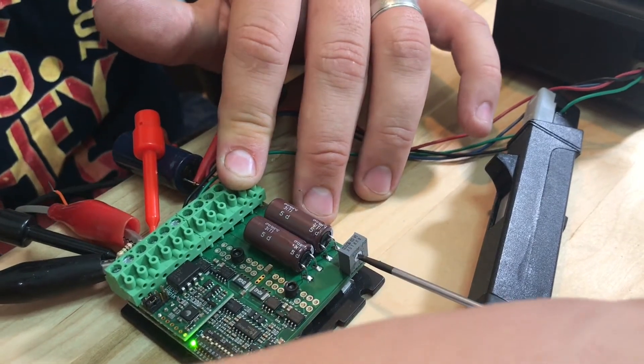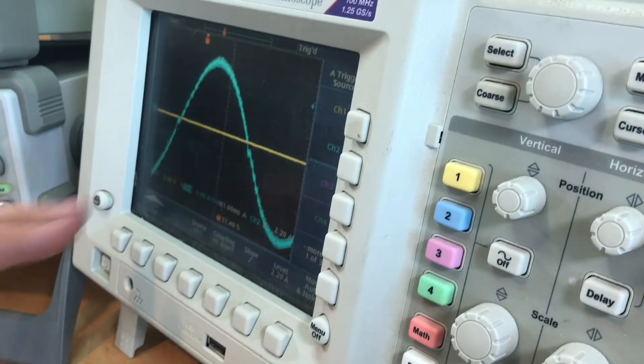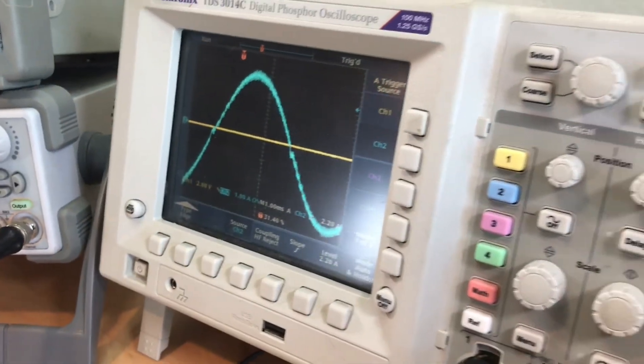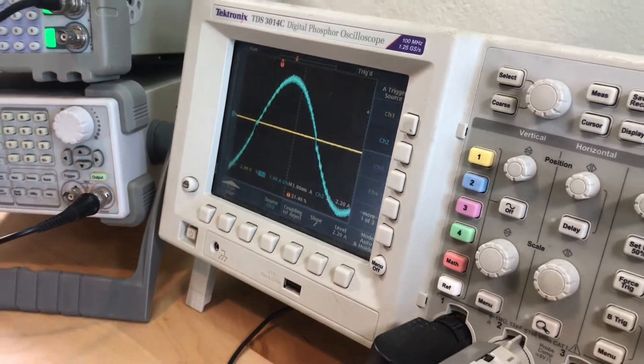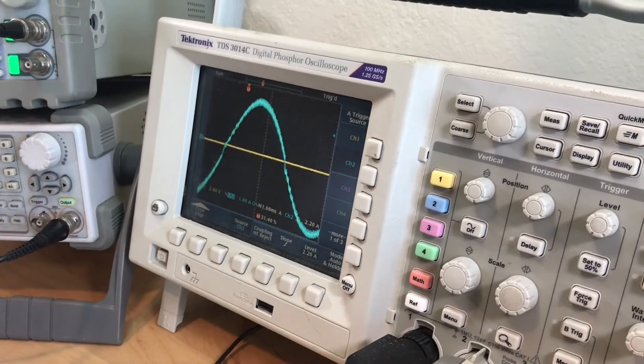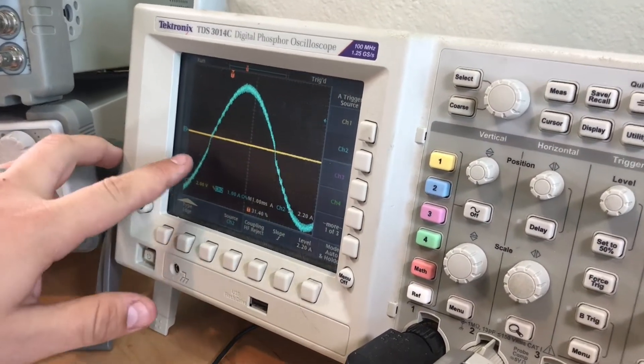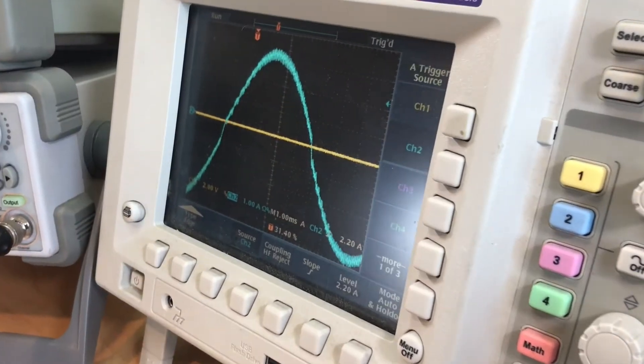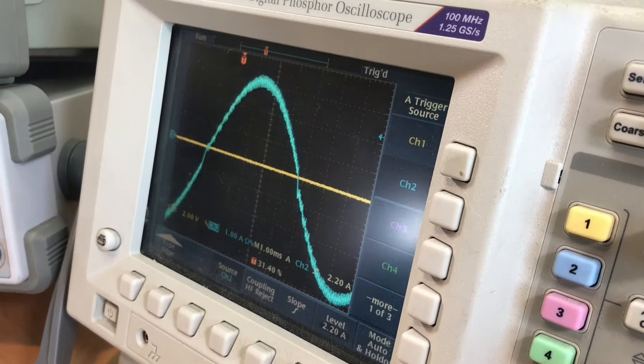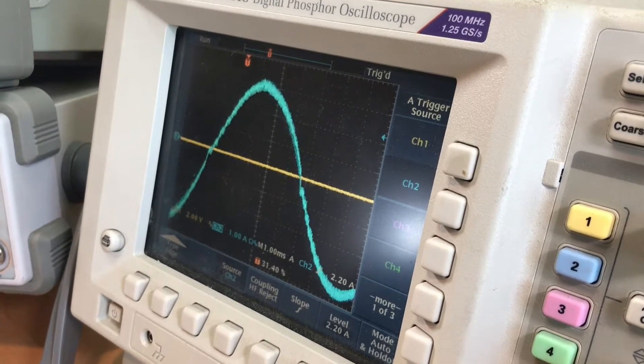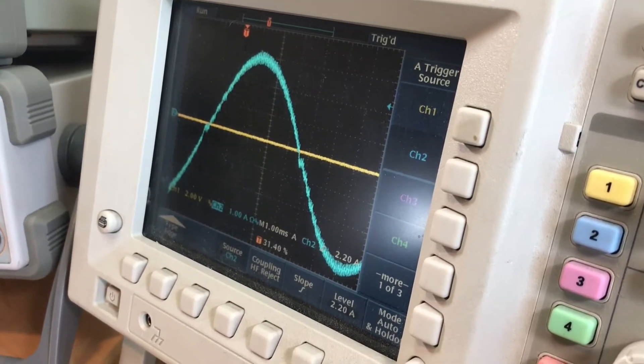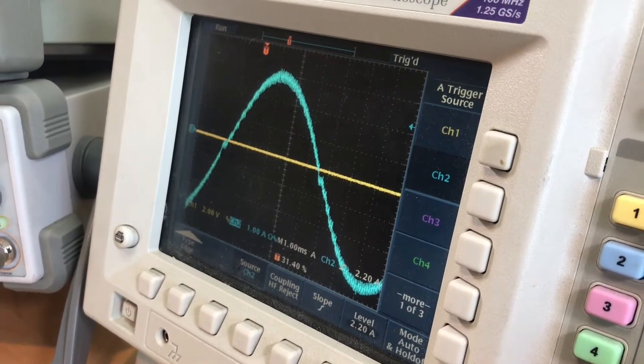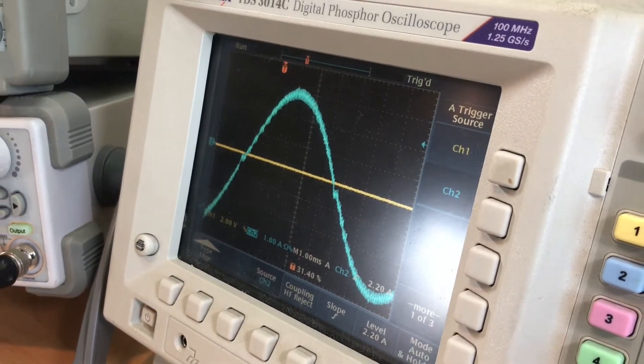So you turn it until the motor reaches a bit of a sweet spot which seems to be about right there. And if you look at the oscilloscope right here, we have a current probe on the motor. And you can see what this is actually adjusting. So when we turn it and it gets loud, you can see the crossover point which is right here expands and that's what the noise is. So we turn it down until that crossover is minimized and it is as quiet as it will be.